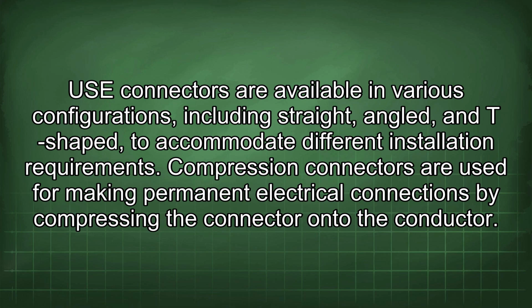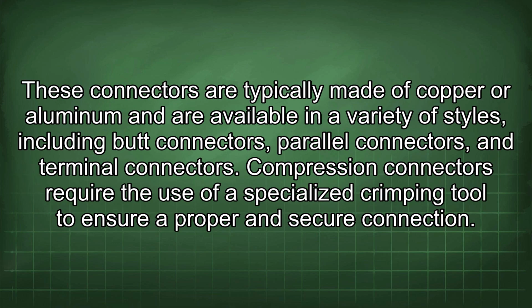Compression connectors are used for making permanent electrical connections by compressing the connector onto the conductor. These connectors are typically made of copper or aluminum and are available in a variety of styles, including butt connectors, parallel connectors, and terminal connectors. Compression connectors require the use of a specialized crimping tool to ensure proper and secure connection.